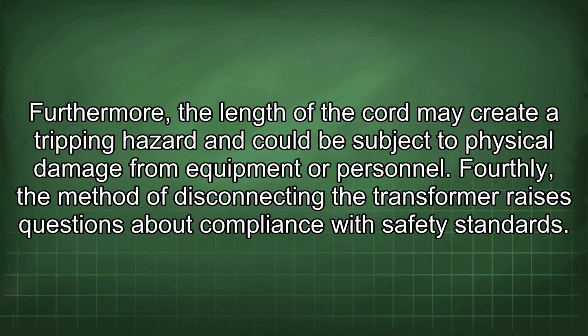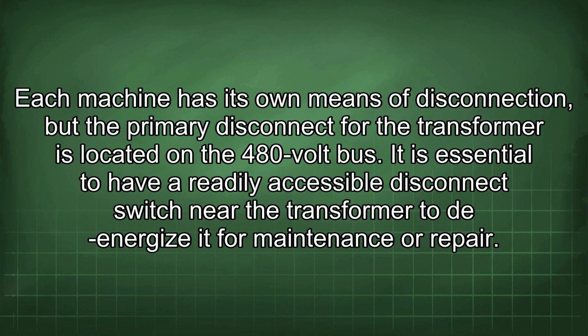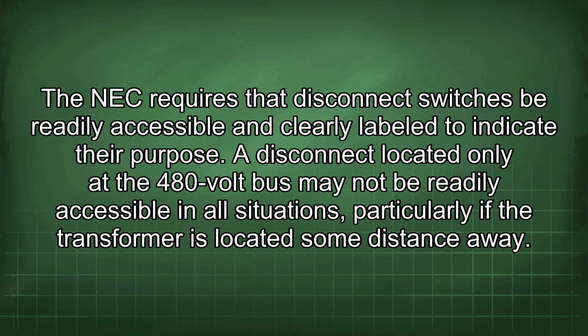Fourthly, the method of disconnecting the transformer raises questions about compliance with safety standards. Each machine has its own means of disconnection, but the primary disconnect for the transformer is located in the 480-volt bus. It is essential to have a readily accessible disconnect switch near the transformer to de-energize it for maintenance or repair. The NEC requires that disconnect switches be readily accessible and clearly labeled to indicate their purpose. A disconnect located only at the 480-volt bus may not be readily accessible in all situations, particularly if the transformer is located some distance away.